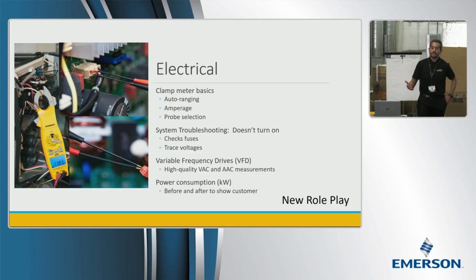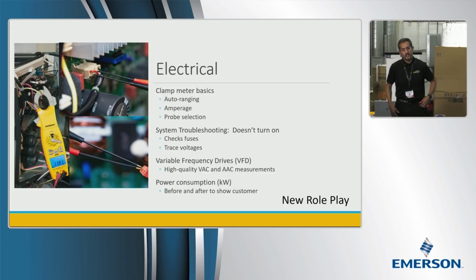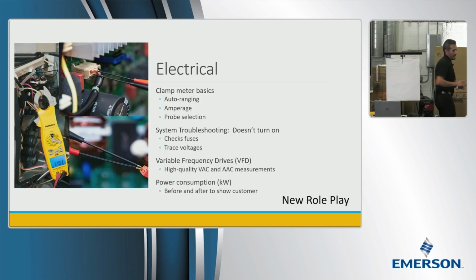Now we arrive on site, we talk to the customer, and the customer tells us, my system's on, but the air is just not as cold as it used to be. At that point, we're probably not going to be checking continuities first. I mean, we could, but we're probably going to look more into airflow and refrigerant charge. I like to start with the non-invasive techniques first and see if I can figure out the problem. So let's go to airflow.